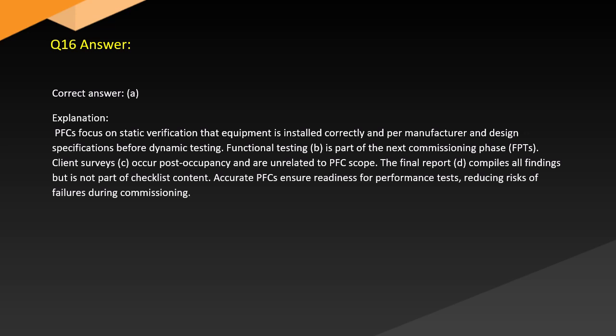Answer. Correct answer. A. Explanation. PFCs focus on static verification that equipment is installed correctly and per manufacturer and design specifications before dynamic testing. Functional testing, B, is part of the next commissioning phase, FPTs. Client surveys, C, occur post-occupancy and are unrelated to PFC scope. The final report, D, compiles all findings but is not part of checklist content. Accurate PFCs ensure readiness for performance tests, reducing risks of failures during commissioning.